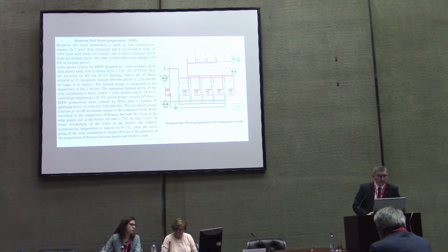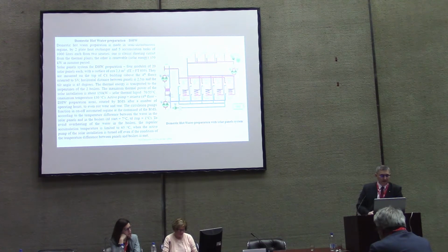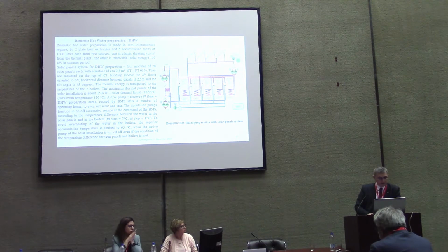Domestic hot water preparation is made in semi-instantaneous regime by 2 plate heat exchangers and 5 accumulation tanks of 1,000 liters each, from 2 sources. One is the classic heating circuit from the thermal plant, and the other is renewable solar energy, 100 kilowatt in the summer period. We have 80 solar panels on the roof of the hospital.